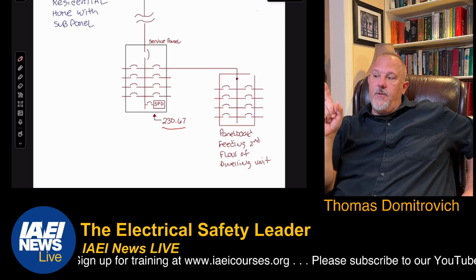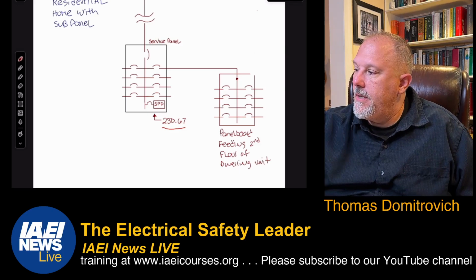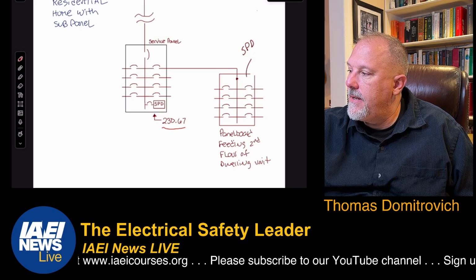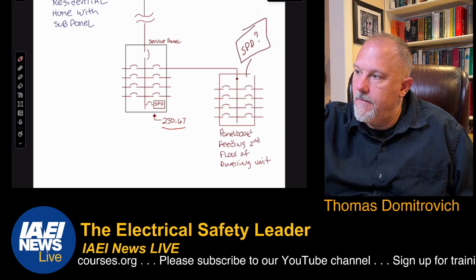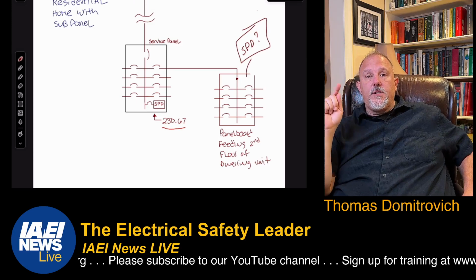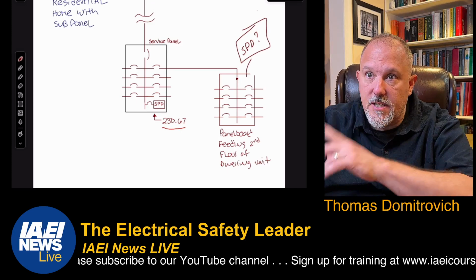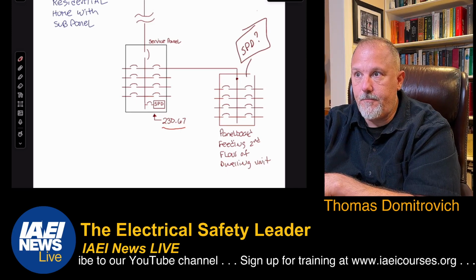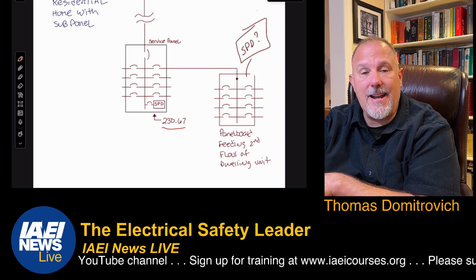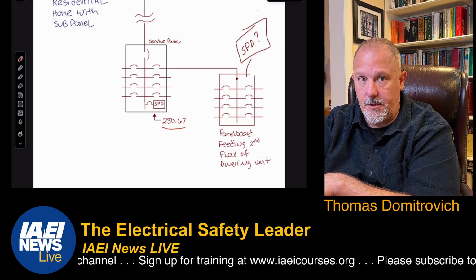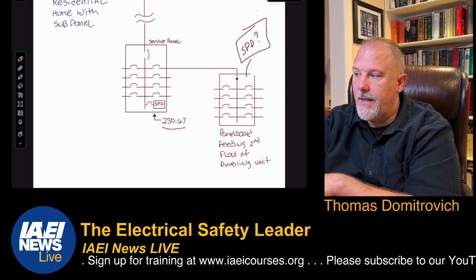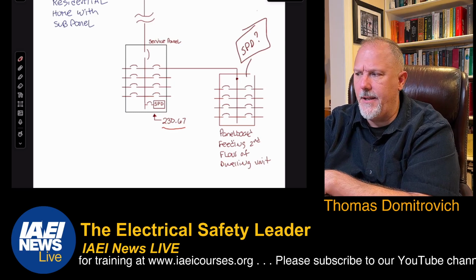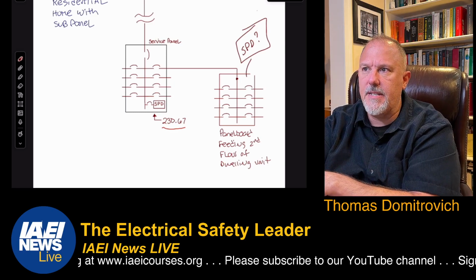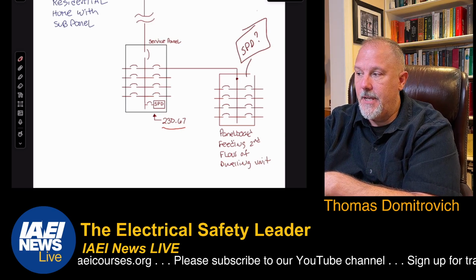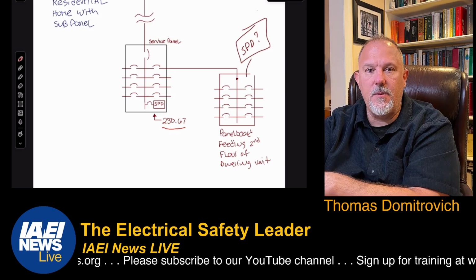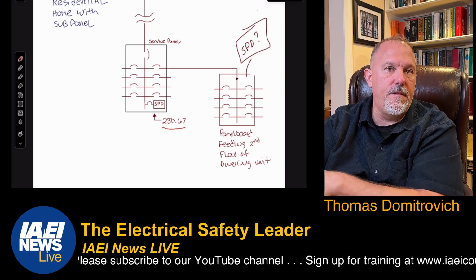The question is, would I need to put an SPD on the second floor? And I've gotten multiple answers from different people. Some people say yes, because of 215.18, that panel board serves the dwelling unit. Now, it doesn't serve the entire dwelling unit, it serves the second floor of a dwelling unit, but it would need an SPD. I have also talked to others who say, no, the code's very clear, where a feeder supplies a dwelling unit. And that feeder does not supply a dwelling unit. It supplies a panel board inside of a home that supplies a portion of the dwelling unit.